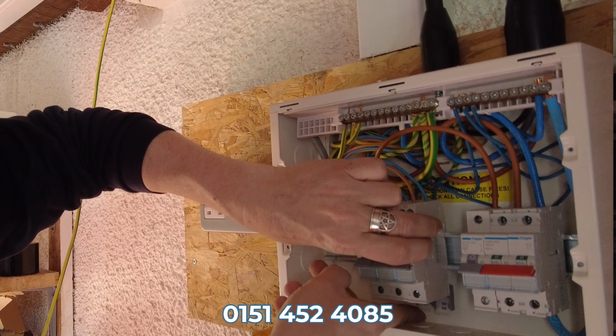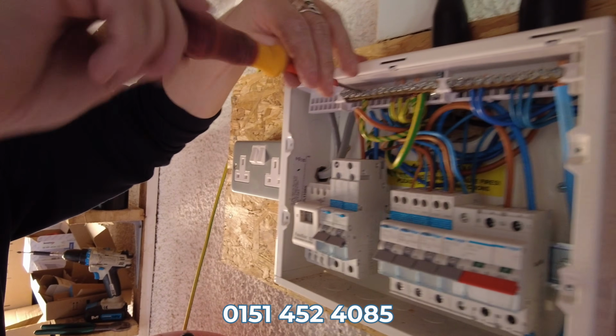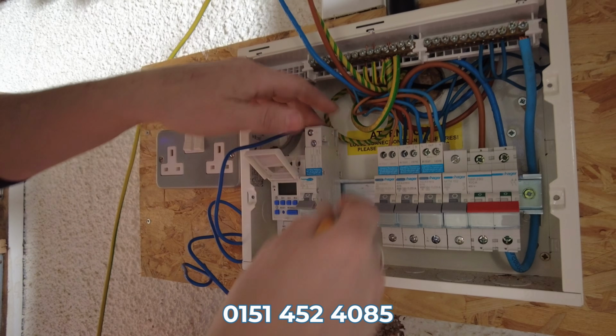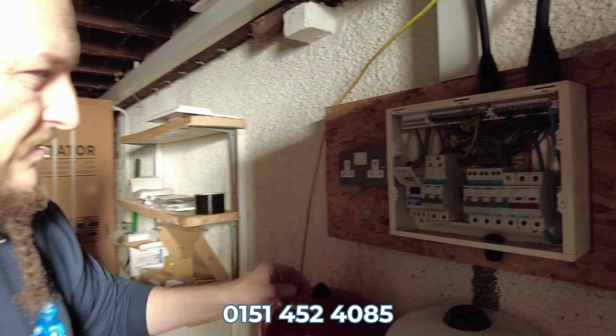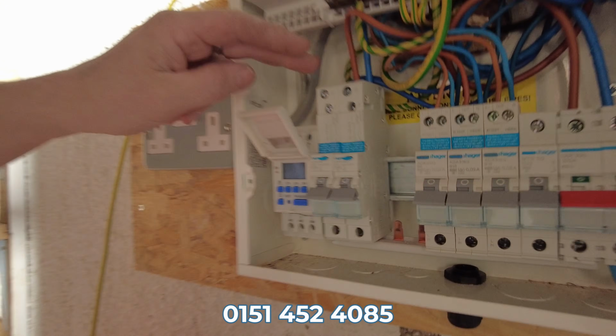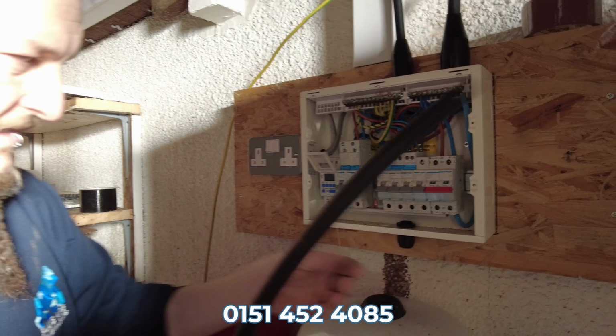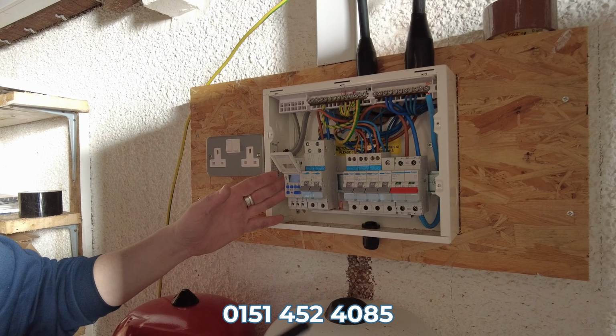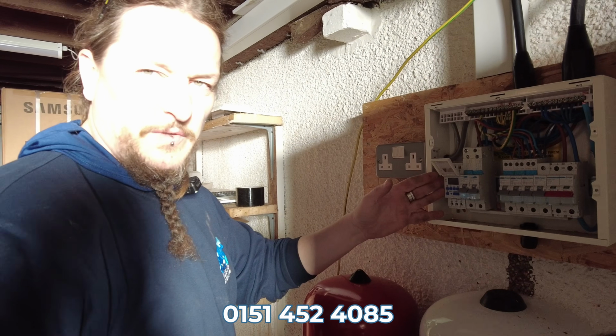I'm just going to fit these now. We'll have one for the immersion heater and one for the air source heat pump. So we've now installed 2 RCBOs, one for the air source heat pump and one for the immersion heater, and I'm just going to bring in the immersion heater cable through the stuffing gland and put it into the timer so that it can do the Legionella cycle once a week.